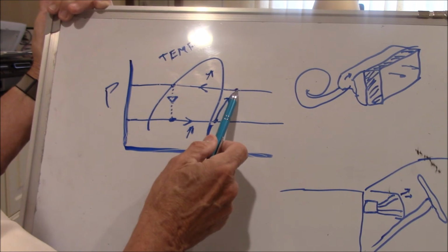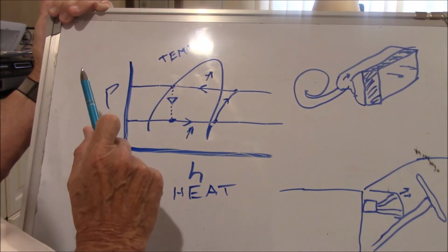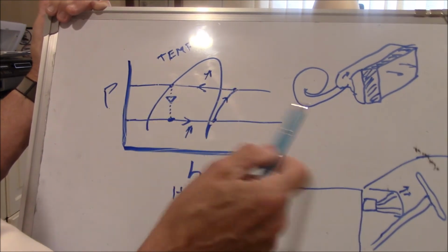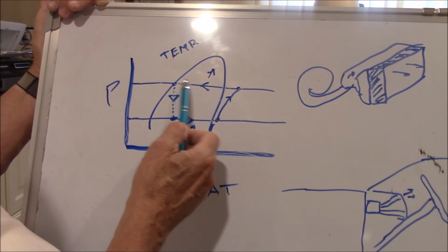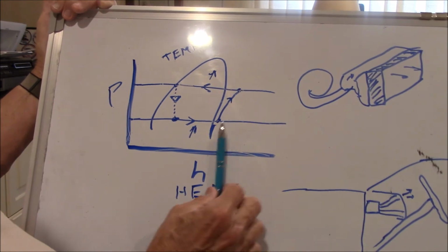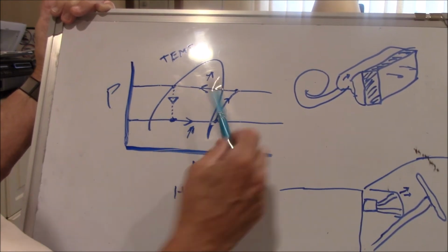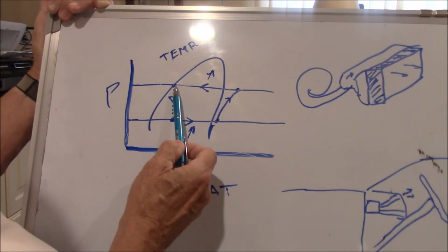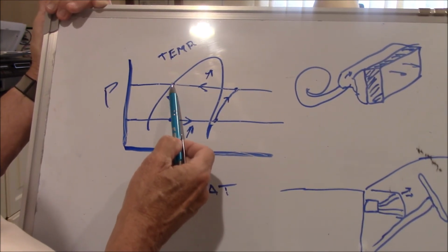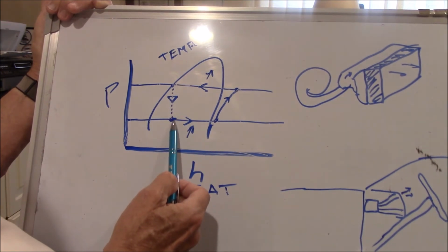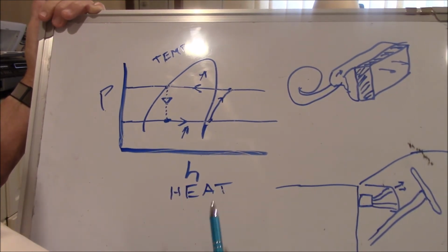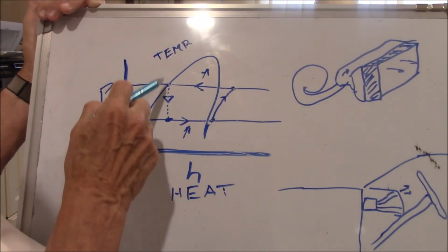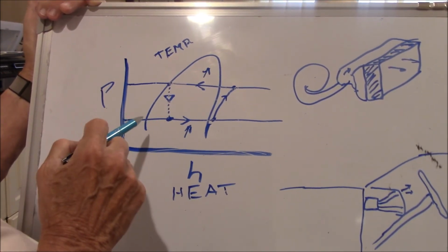Then you run that through the heat exchanger that is outside your house. And as you run it through that heat exchanger that I described, it gives up heat. It's rejecting heat. Heat is going out into your atmosphere. And then when it gets over here almost all liquid, we expand it down through either an expansion valve or capillary tubes, but it's a restriction that lets it spill down to the lower pressure.